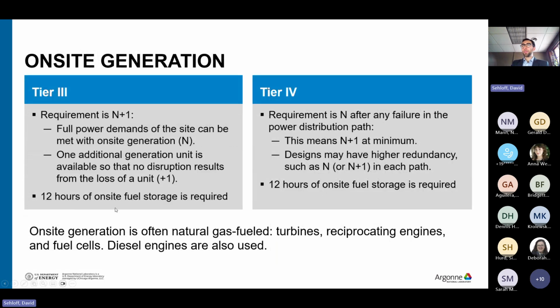Just a little bit more detail: for tier 3, there's a requirement of N+1 on-site generation. That means for N, we have the full demands of the site met with on-site generation for the servers and the cooling equipment, and then there's one additional generation unit so that we don't have a disruption if we lose one unit. Under this, there's also a requirement for 12 hours of on-site fuel storage.